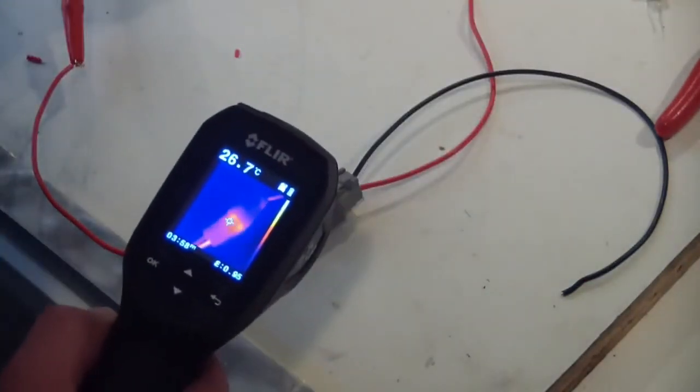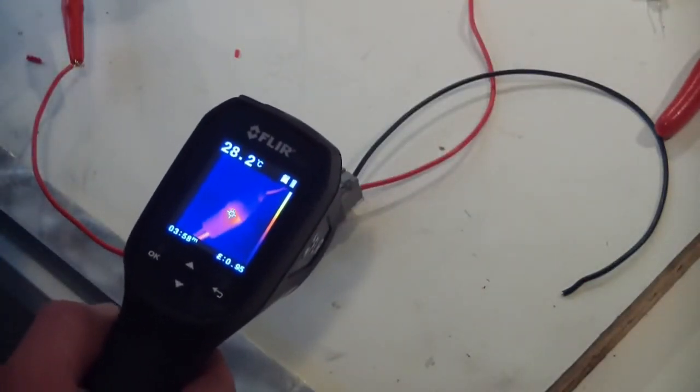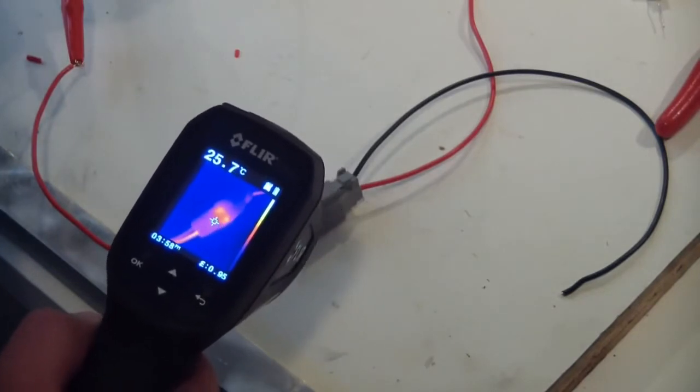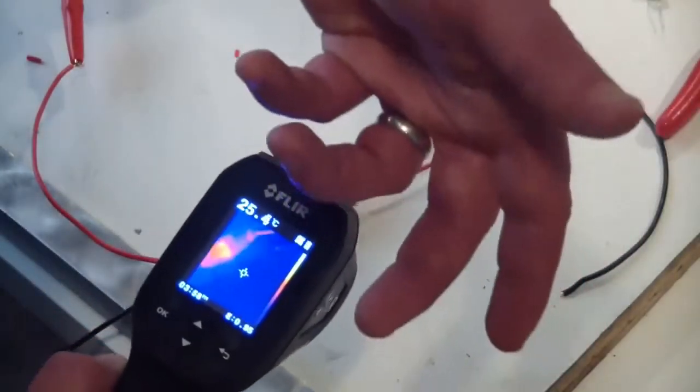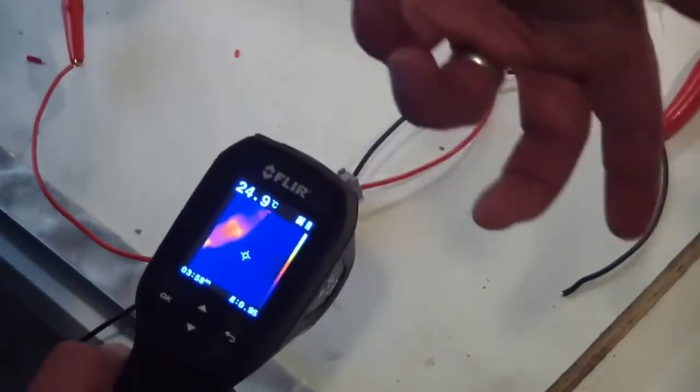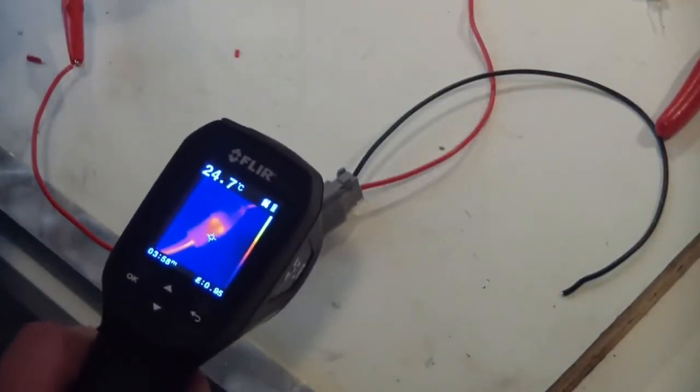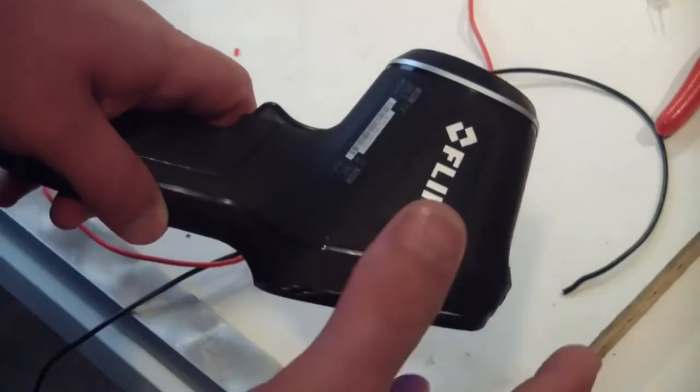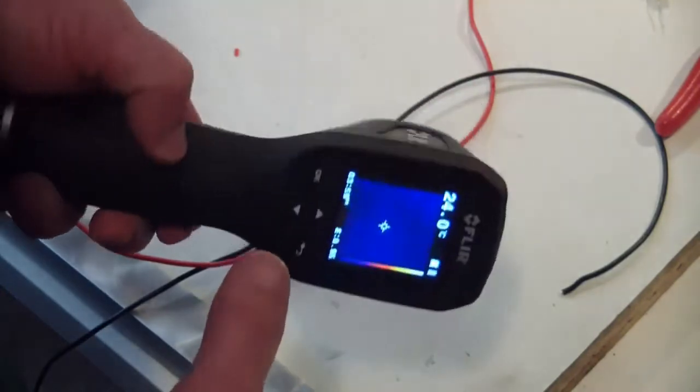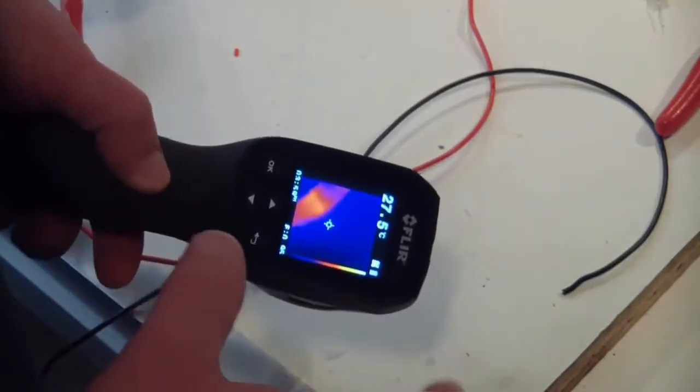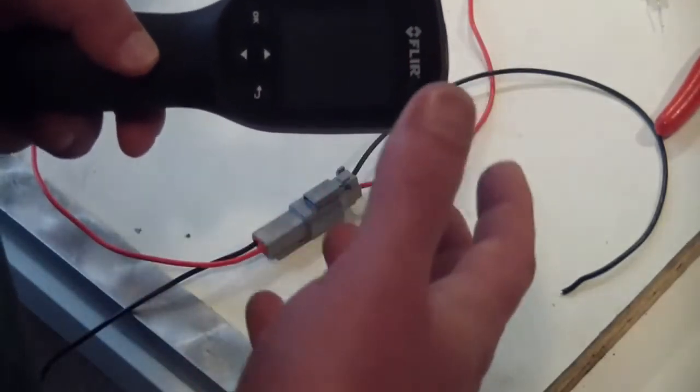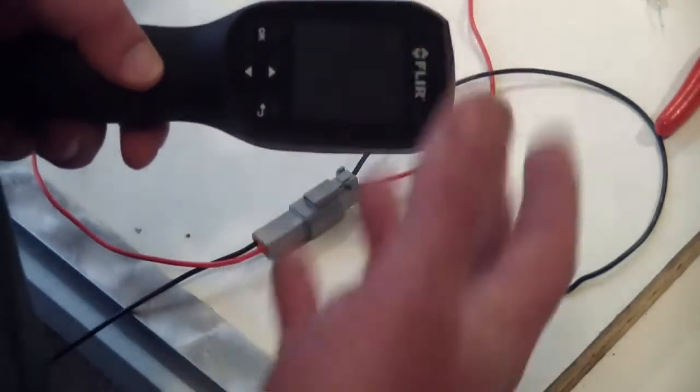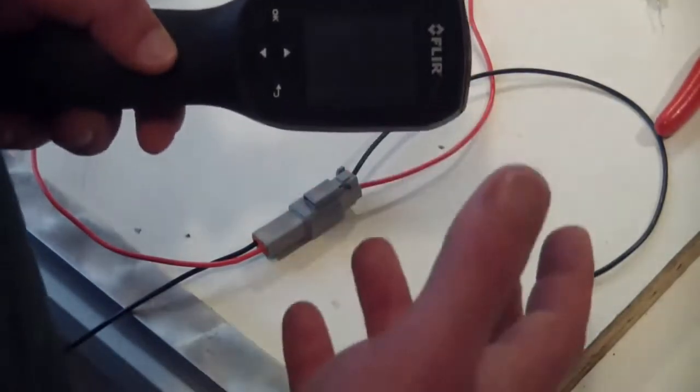What you can also do is go around and take shots and save them for later so that when you think there's a problem, you can go back and look at your old pictures to see if it was running hot before. So this is going to be a relatively cheap and easy way to quickly check for hotspots on your problem items. Once you find your problem spots, you can go ahead and use your meter to confirm that your hypothesis is correct.